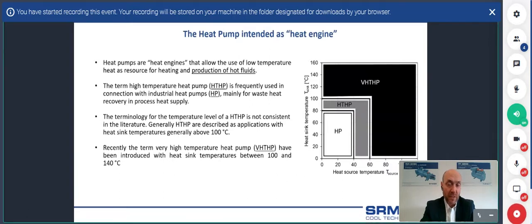For the people that don't know, a heat pump can be defined very simply as a heat engine that uses a refrigerant cycle to produce hot fluids. In this family of systems, we can differentiate the common heat pumps that everyone can find in household installations, with a split installed in the houses, where the maximum heat sink temperature is normally about 80 degrees C. Above these values, we start to define the systems as high temperature heat pumps, which commonly produce fluids up to 100 degrees C.